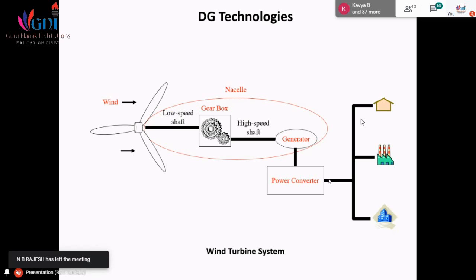Whenever you need to have an interconnection of any generator with the grid, it has to follow the norms of synchronization. What are these norms? The voltage of the generator and the system to which you are connecting it should be matched. The frequency should be the same, and the phase sequence should be the same. If these three conditions are satisfied, only then can you synchronize your generator with the utility.